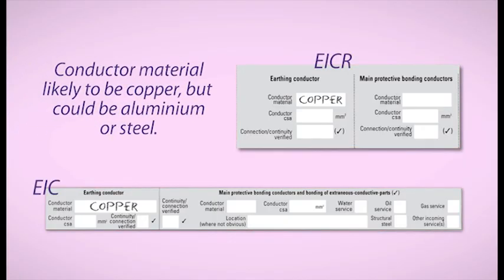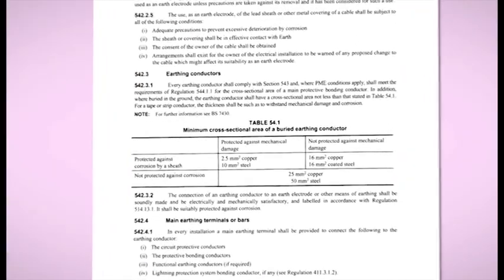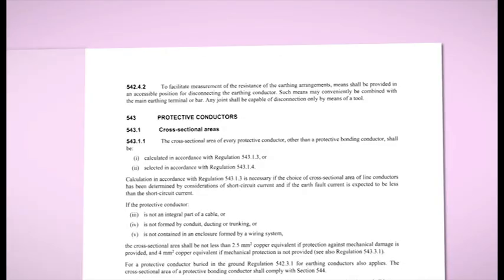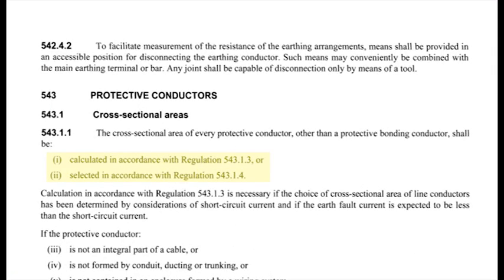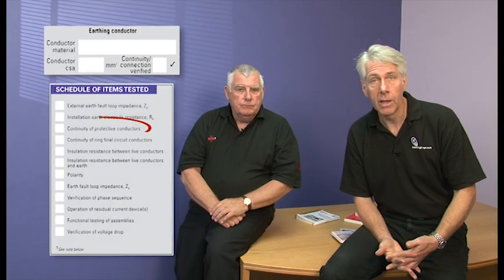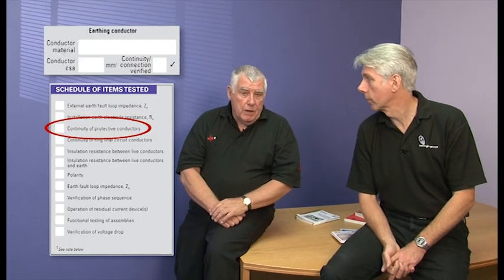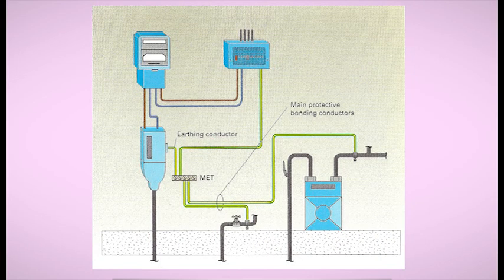The conductor material will generally be copper, but it could be aluminium or steel, and the cross-section area needs to comply with the requirements of Regulation Group 542.3 and Section 543. Here you will find detailed information on how you can either select a suitable cross-section area or calculate it. Within the section concerned with protective conductors, there is a box to confirm that both the connection and continuity of the conductor has been verified. This could either be a visual means of checking continuity or confirmed by testing. Just to let you know that when we say visual check, we mean that you can see the entire length of the conductor. So even though it might only be for a couple of metres, if it passes through a wall at any time, you will have to confirm continuity by measurement.